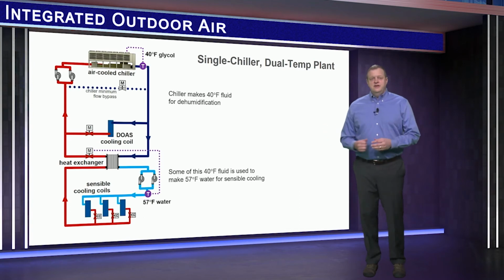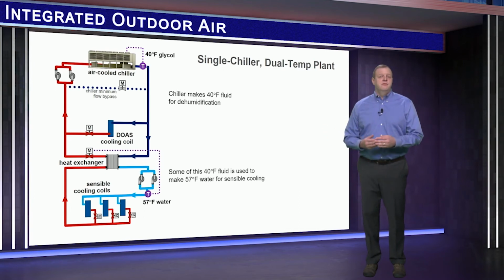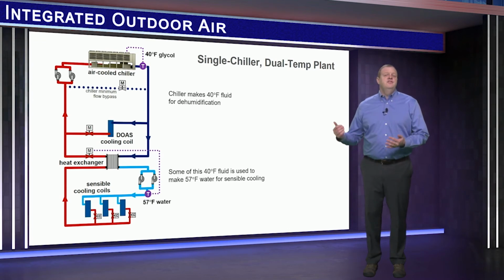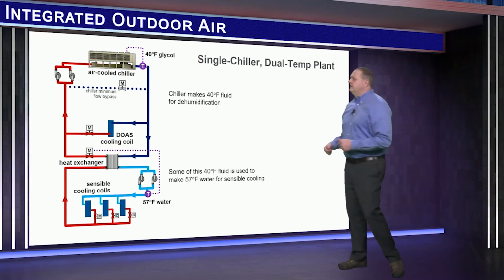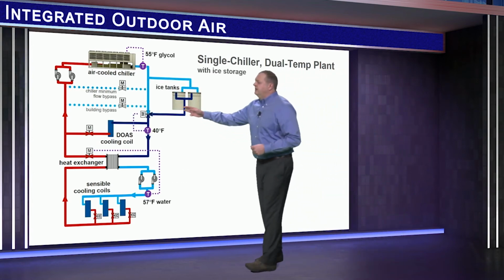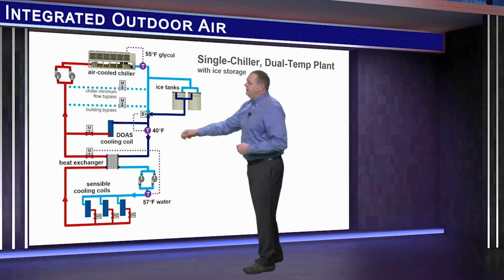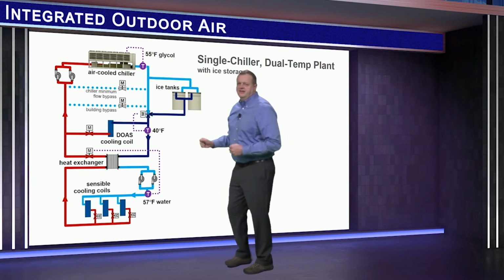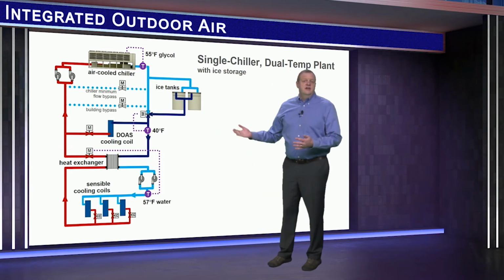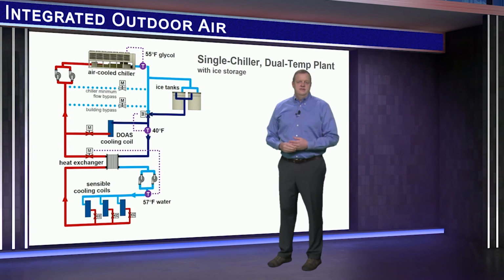Okay, I said this single chiller configuration is simple, but the chiller needs to make 40-degree fluid whenever outdoor conditions require dehumidification. So you don't get any efficiency benefit of operating a chiller at the warmer temperature used for sensible cooling. One way to gain that efficiency benefit is to use more than one chiller. We show those configurations in the system catalog. But another way is to add ice storage to this single chiller plant. First, we pipe in the tanks and a blending valve downstream of the chiller. And we add a building bypass pipe for charging the tanks at night. So far, this is just like a regular air-cooled chiller with ice, which we've been doing for decades.